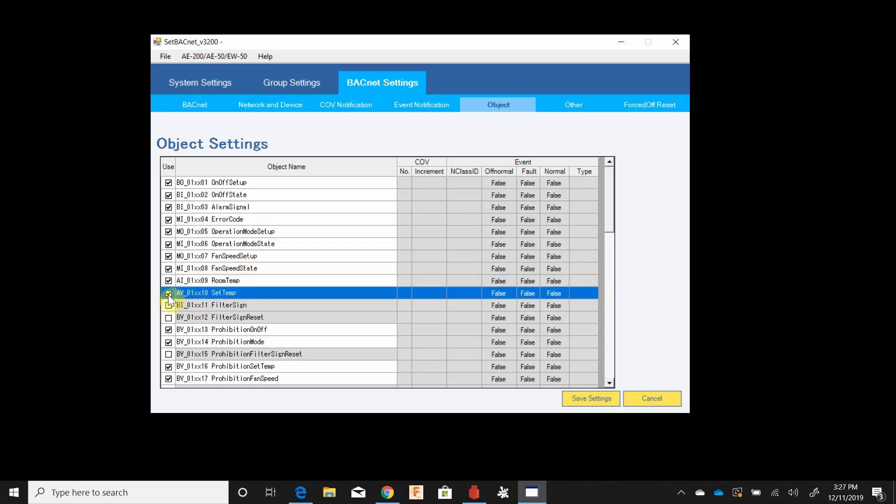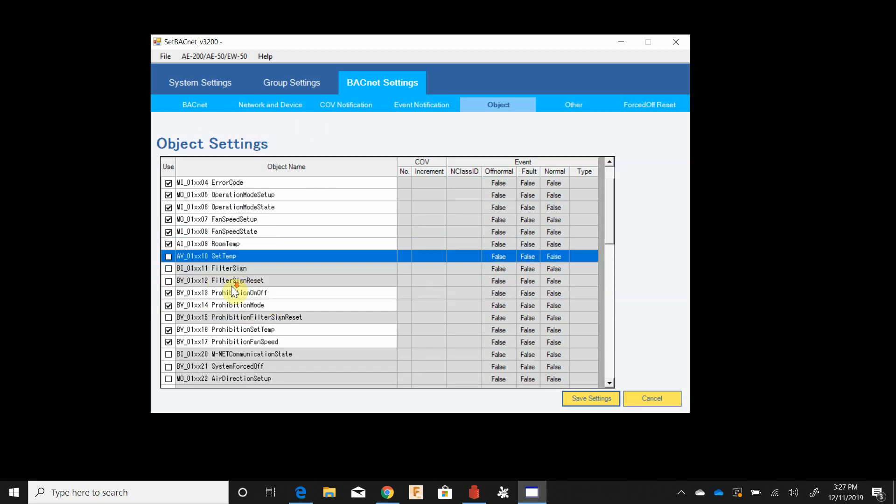This one is checked right now but it needs to be unchecked. This set temp is only applicable if the old model compatibility mode is on. This is listed in the BACnet manual on my link drive for the AE-200 and it is only compatible with single set point old compatibility mode.